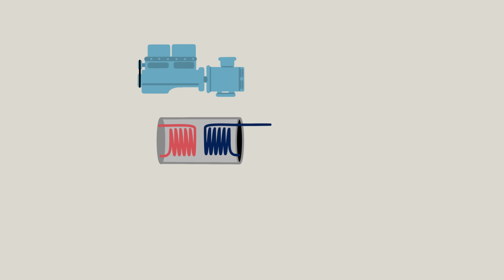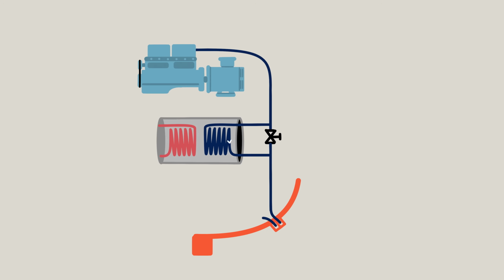For starters, we want to use engine heat to warm up the potable water and the floor heating, which is not uncommon. You can do this with separate heat exchangers, but to save space and keep things simple, we chose a buffer tank with 2 internal heat exchanger coils, through one of which we plan to have warm engine coolant flow before it goes to the bilge keel coolers. That way, the engine coolant can heat up the potable water to a maximum of 80 degrees Celsius. The other coil we'll use for the heated floors, but more on that later.